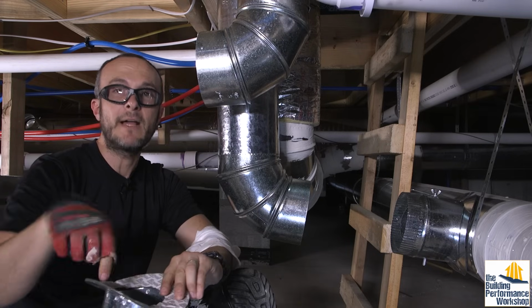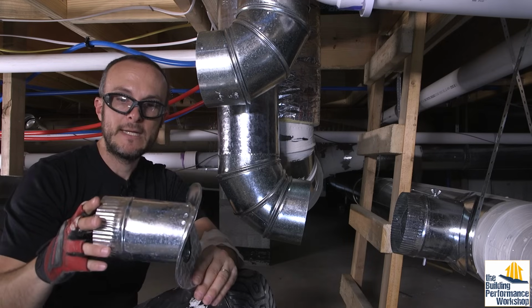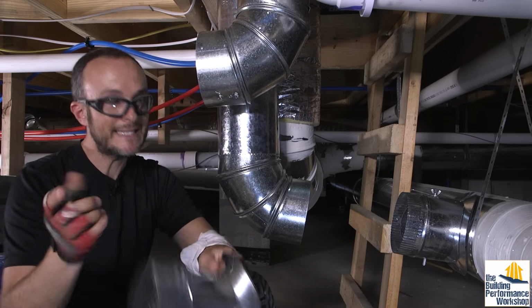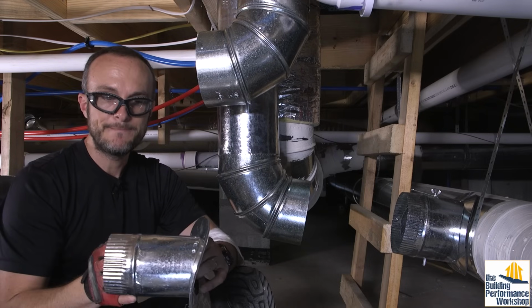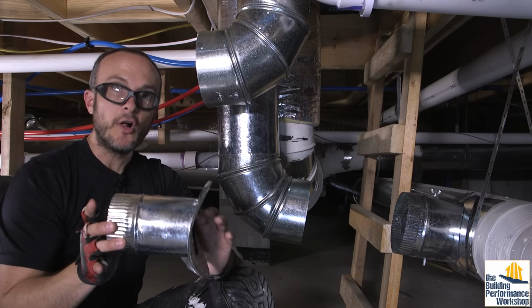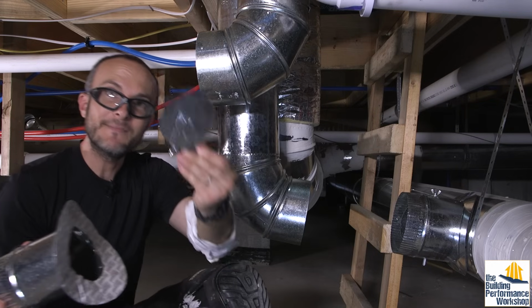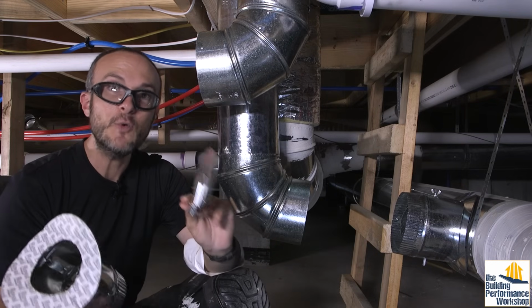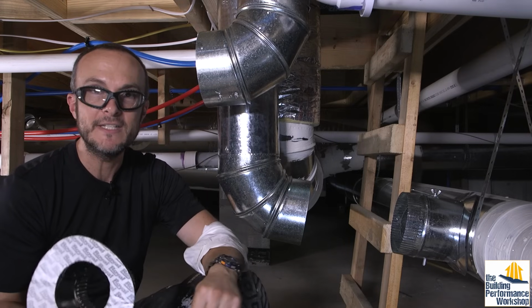And so I would make my hole with my drill mount hole cutter, and then I put this on there. Now this is made out of a bunch of different pieces of metal, so I'm going to need to seal it just like you can see all these things are sealed with plenty of mastic. But that's not all. You're going to want to have inside of this another very important piece of equipment. It's called a damper. Does not cost a lot of money. Please do ask for dampers to be put in on every single takeoff of a duct.